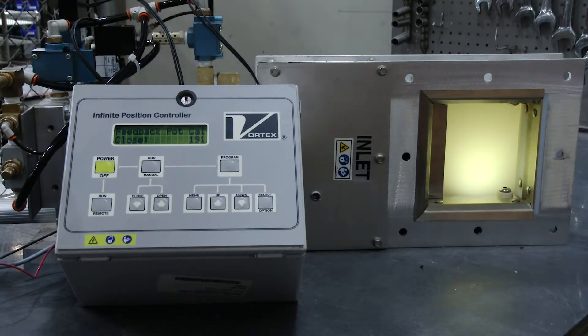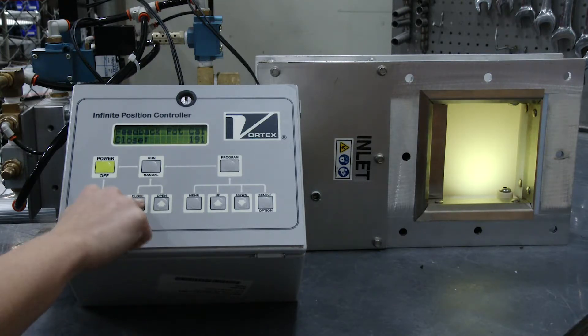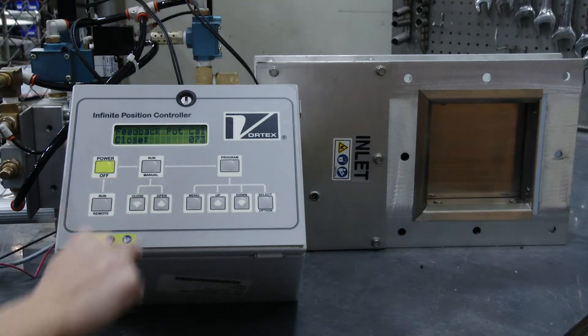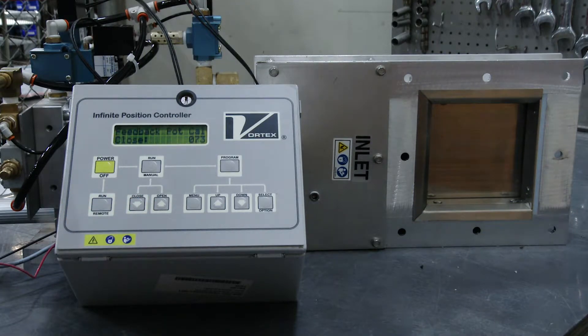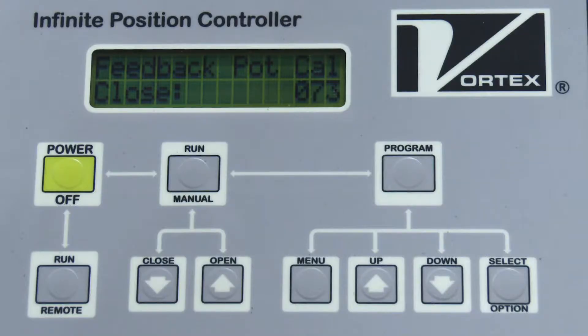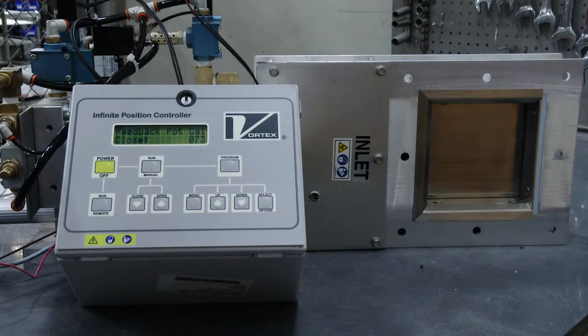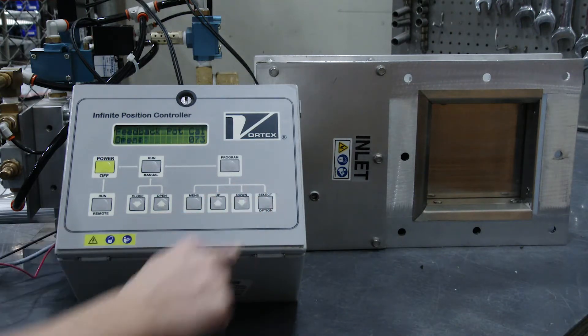As prompted by the IPC, we will calibrate the closed position first. Press the Close button under the Run Manual button, even if the valve is already in the closed position. Notice the number in the lower right portion of the display. This number is representative of the valve gate position on a scale of 0 to 255. Once the valve is in the fully closed position, press the Select Option button.